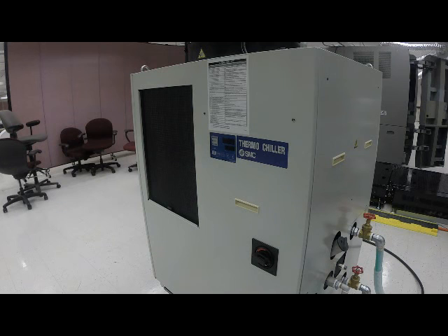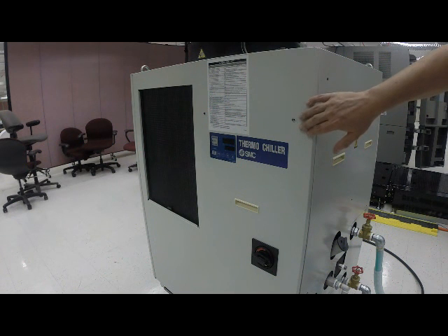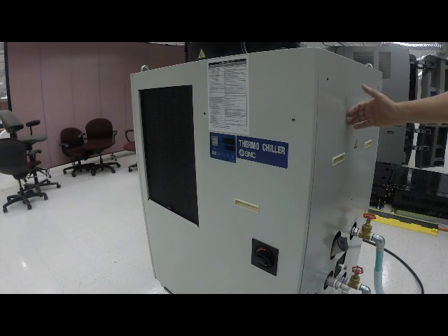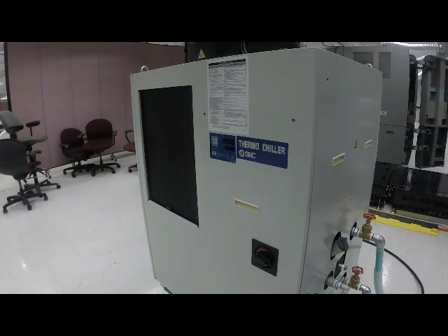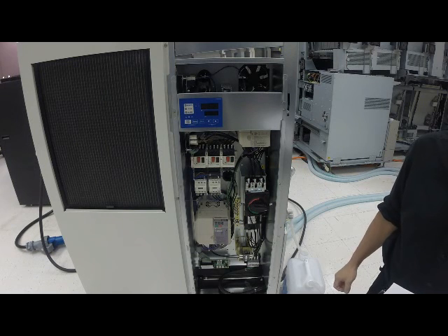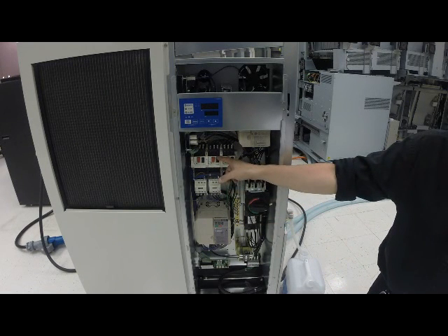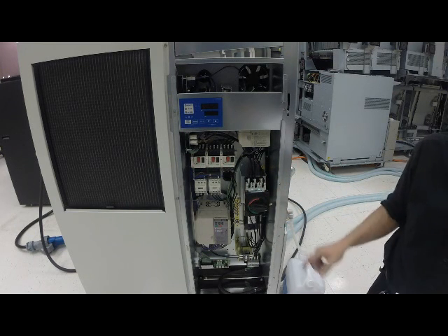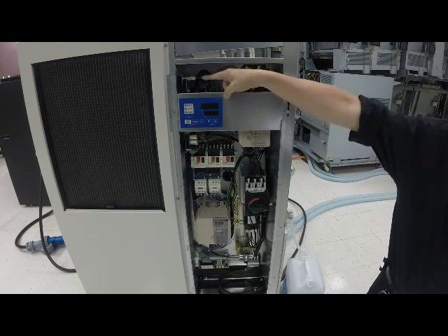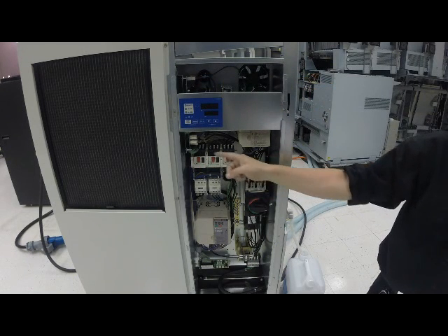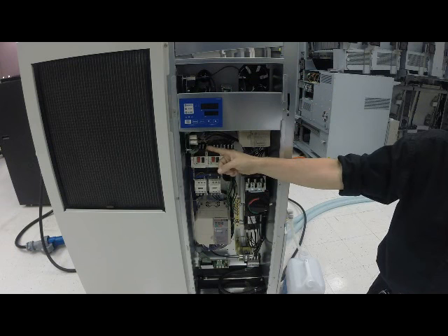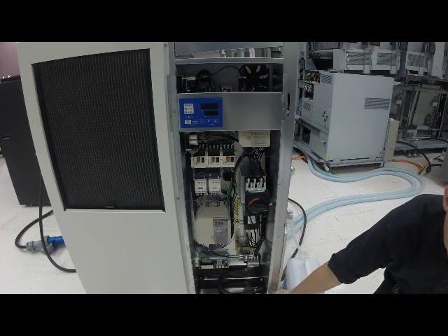The service covers must be removed in a specific order as listed in the service manual. Start with the front panel for the electrical unit and then continue on to the upper side panel. The remaining three covers may be removed as needed. Inside the front cover, you can see the earth leakage breakers, which may need to be switched on at installation. The display unit is covering most of the main circuit board at the top, and underneath that is the interface board. The power terminal strip near the bottom of this unit is where the power cable will need to be attached at install.